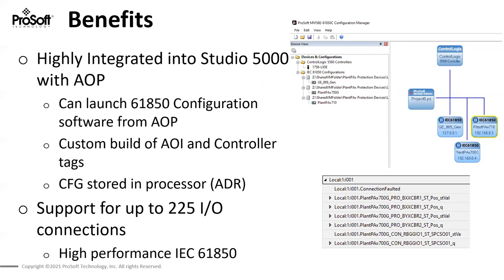The nice part about everything being integrated within an add-on profile is that it's stored directly in the processor. In the event of a device failure and you need to plug in a new module, automatic device replacement means you plug in the new module, it gets the configuration from the processor, and you're back up and running. The 225 IO connections and the ability to define some as high-priority connections is a great enhancement for this solution.